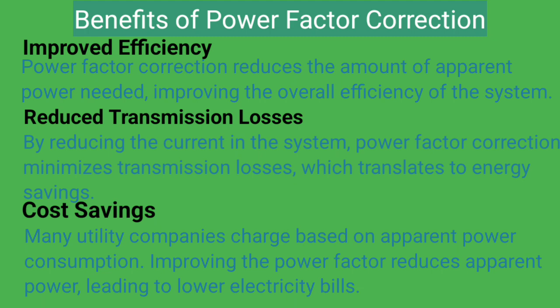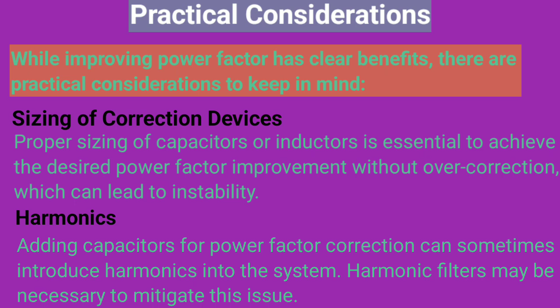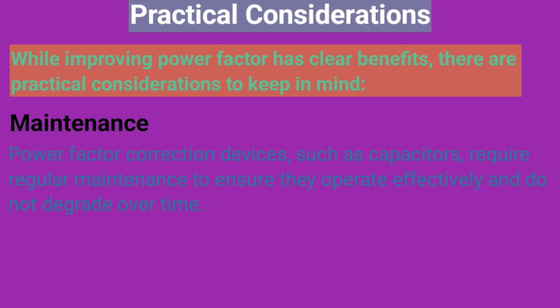Practical considerations. While improving power factor has clear benefits, there are practical considerations to keep in mind. Sizing of correction devices. Proper sizing of capacitors or inductors is essential to achieve the desired power factor improvement without overcorrection, which can lead to instability. Harmonics. Adding capacitors for power factor correction can sometimes introduce harmonics into the system. Harmonic filters may be necessary to mitigate this issue. Maintenance. Power factor correction devices, such as capacitors, require regular maintenance to ensure they operate effectively and do not degrade over time.